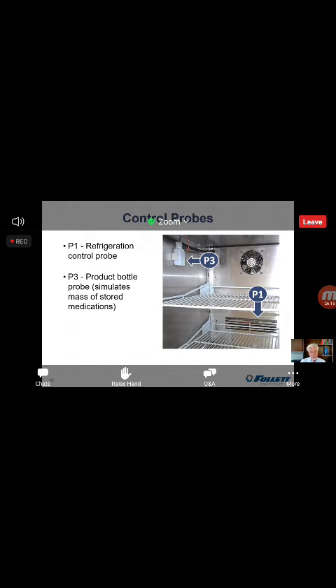And as I mentioned, refrigerators have 2 probes, freezers have 3. On the refrigerator, we call the refrigeration control probe P1. This is the one that actually controls the temperature of the unit, controls when the refrigeration system runs. The P3 probe is in the bottom. This does nothing more than report, so they're completely independent. They do not communicate with each other in any way. P1 controls, P3 reports. This is the temperature we're showing in the display, and this is also the one that we use for temperature alarming.